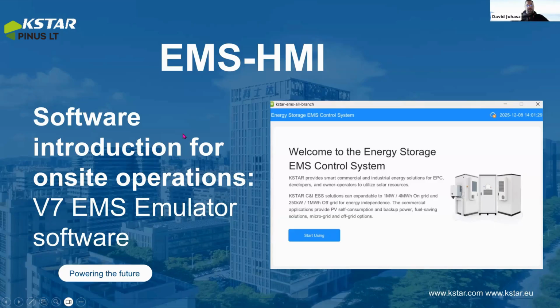Is there an ATS available? We choose no. And we need to select the type of the cabinet capacity. Next, we can set here, for example, the 197. And it is asking us, is there a cabinet next to it? You can see it's a single device now. And we need to choose the inverter type. Is it simple DP for on-grid solutions or DP2 for off-grid solutions? And we can give the number of these inverters.